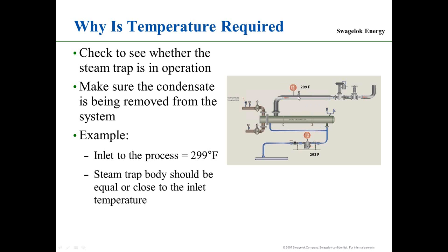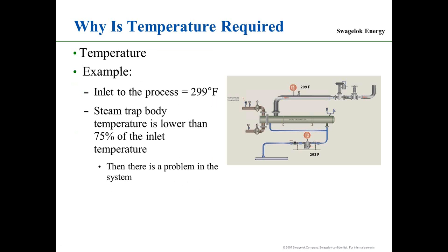Yes. But always make sure you take an inlet to the process temperature and a steam trap body temperature. I'll tell you that your steam trap is in operation. And that's the beginning of the process. If you take an inlet temperature of 299 and your steam trap body temperature is 75% or lower than the inlet temperature, then I want you to stop, because there's something wrong. Don't even proceed to the next step, which is using the ultrasonic unit. So temperature is critical.